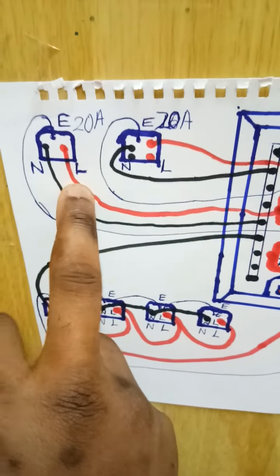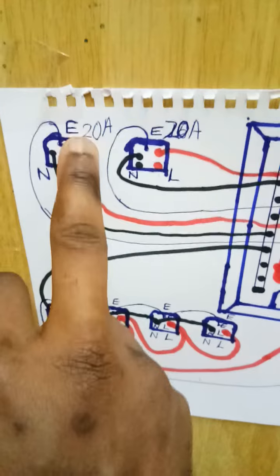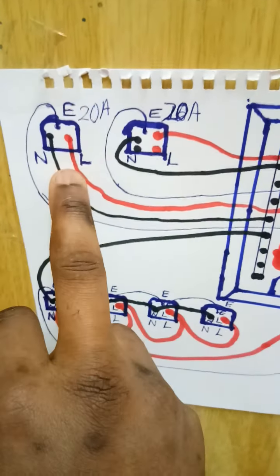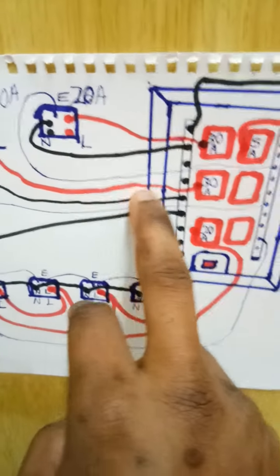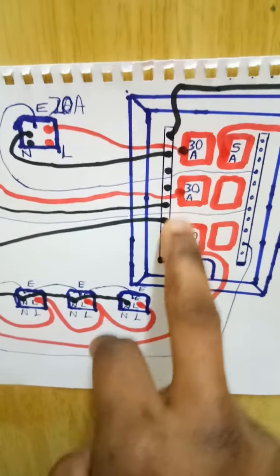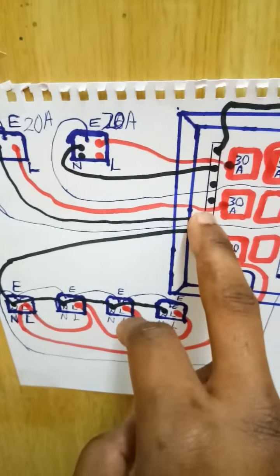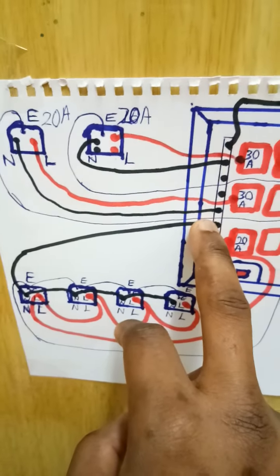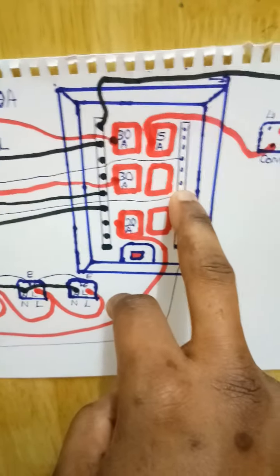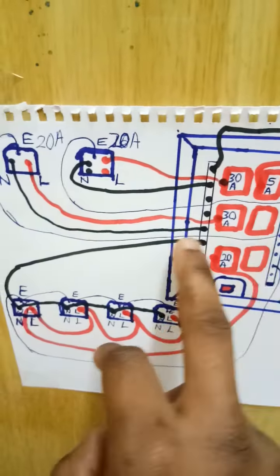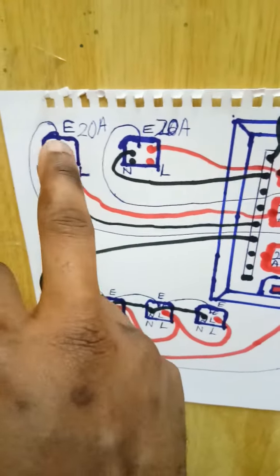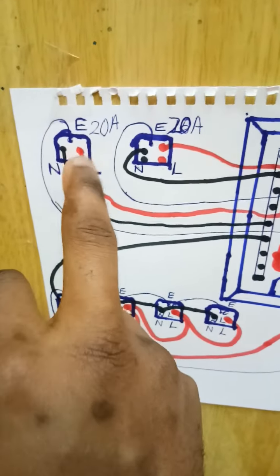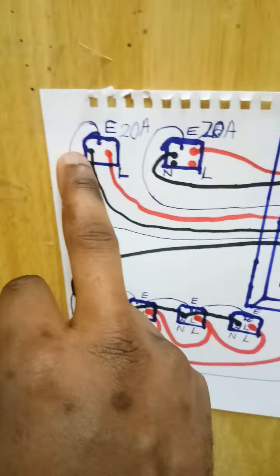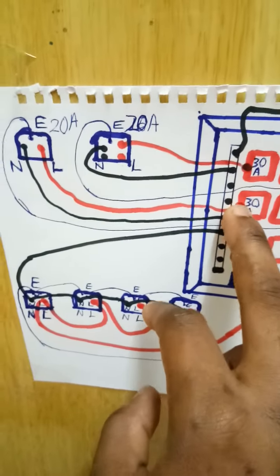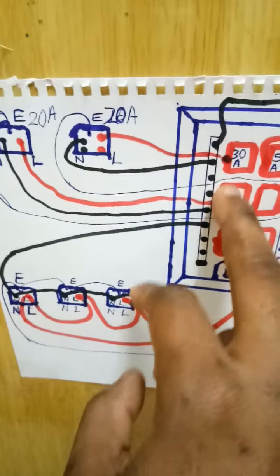As you come over here, you see this is the AC switch. This is rated 20 amps, but 15 amps is okay. As you can see, the live wire of this AC switch goes direct on its own to a 30 amp circuit breaker. Then its neutral comes to the same place that the neutral of the socket comes to. Then the earth still goes to the earth rail. This 15 amp socket for AC has its own circuit breaker, only one circuit breaker for one AC. One AC must have one circuit. So if anything goes wrong with this 30 amp circuit breaker, the others will be working.